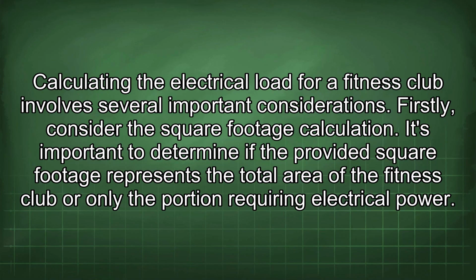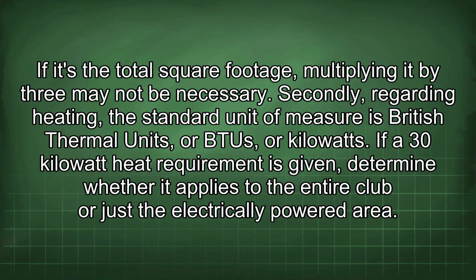Calculating the electrical load for a fitness club involves several important considerations. Firstly, consider the square footage calculation. It's important to determine if the provided square footage represents the total area of the fitness club or only the portion requiring electrical power. If it's the total square footage, multiplying it by 3 may not be necessary.